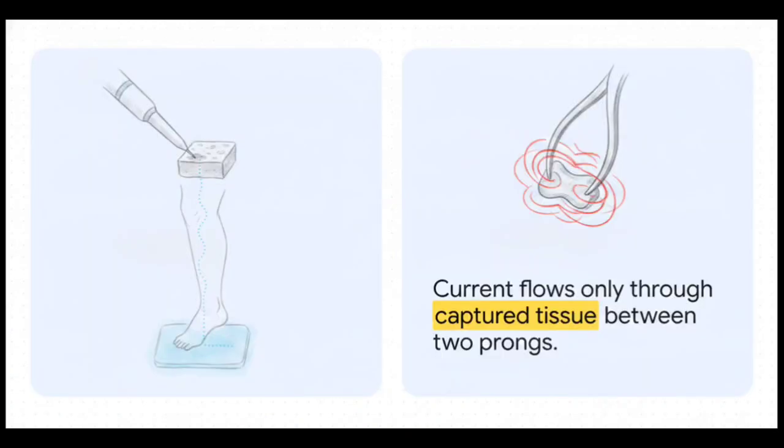This is a fantastic illustration of how that current actually travels. On the left, we've got monopolar diathermy. Here, the current travels from a single active electrode right through the patient's entire body and exits safely via a massive dispersive return pad on their skin, routing back to the generator.